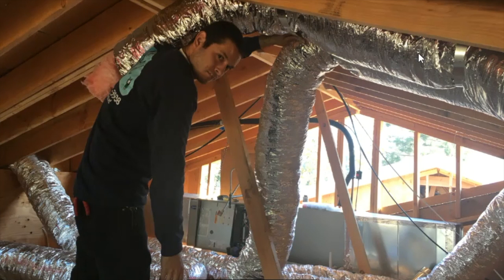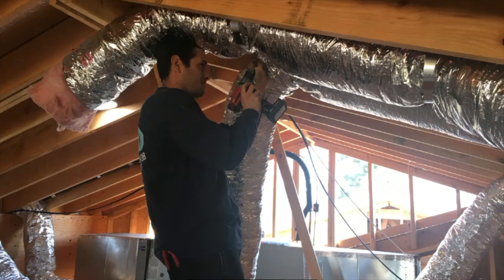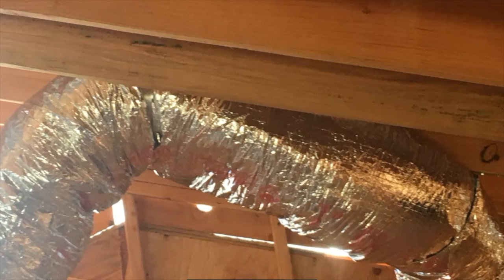Here's David strapping up the duct as we're working our way back towards the equipment. We're keeping everything strapped every 3 feet per code and then securing it up in the rafters because the homeowner wants to use the attic space for a work area and storage area. David's using his screw gun here to secure the strap to the roof rafters. Another picture of the duct secured.